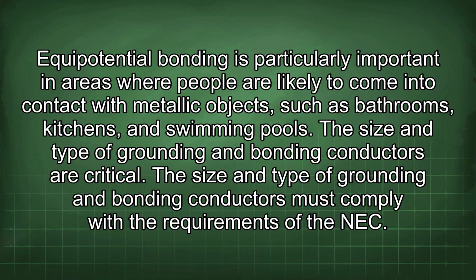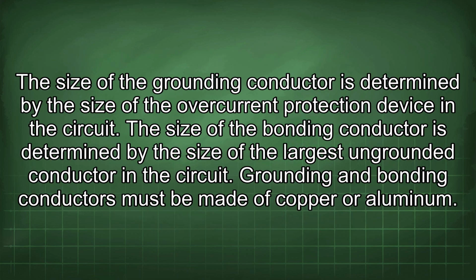Equipotential bonding is particularly important in areas where people are likely to come into contact with metallic objects, such as bathrooms, kitchens, and swimming pools. The size and type of grounding and bonding conductors are critical. The size and type of grounding and bonding conductors must comply with the requirements of the NEC. The size of the grounding conductor is determined by the size of the overcurrent protection device in the circuit. The size of the bonding conductor is determined by the size of the largest ungrounded conductor in the circuit.